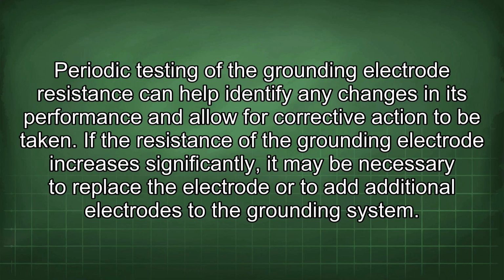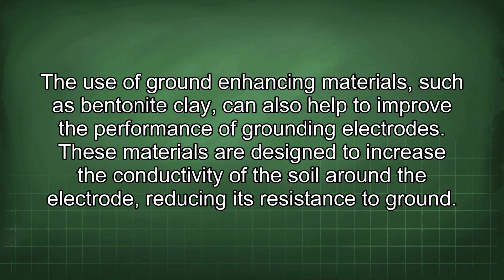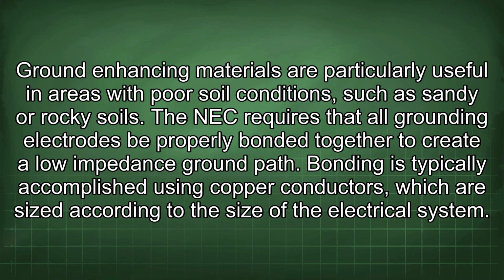Periodic testing of the grounding electrode resistance can help identify any changes in its performance and allow for corrective action to be taken. If the resistance of the grounding electrode increases significantly, it may be necessary to replace the electrode or to add additional electrodes to the grounding system. The use of ground-enhancing materials, such as bentonite clay, can also help to improve the performance of grounding electrodes. These materials are designed to increase the conductivity of the soil around the electrode, reducing its resistance to ground. Ground-enhancing materials are particularly useful in areas with poor soil conditions, such as sandy or rocky soils.